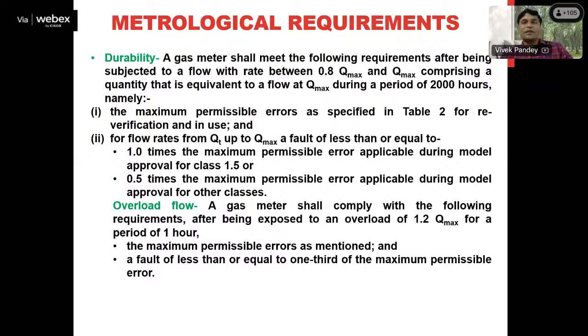Now, the next important metrological requirement which I'm discussing is called durability of the gas meter. This is a test which we perform on the gas meter during model approval as well as initial verifications. What we do basically during this test is try to check the reliability of our instrument, meaning how durable it is, how many years we can use it without its accuracy being affected. In the durability test, we run our gas meter between a flow rate of 0.8 times Q maximum to Q maximum. We can decide any flow rate. We can also run it at Q maximum flow rate.